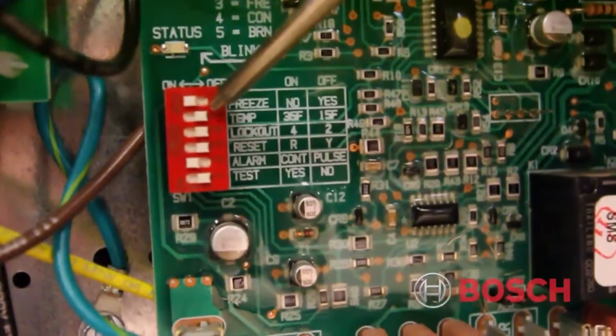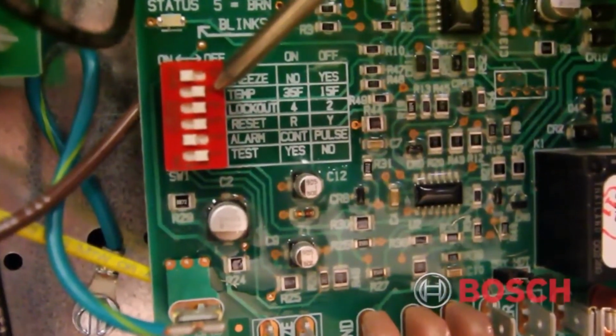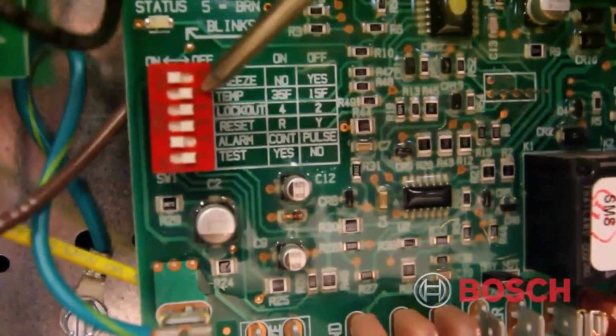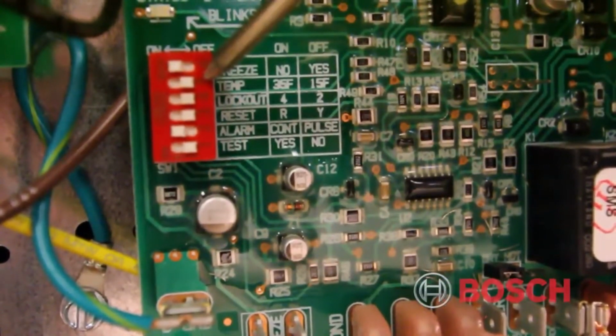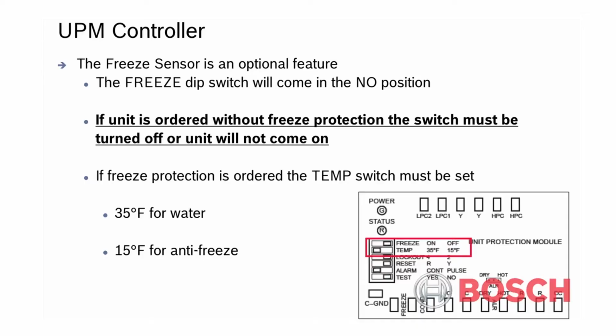The next switch has to do with the temperature cutout of that freeze protection. There are 2 settings, one at 35 degrees and one at 15 degrees. 35 degrees should be selected for systems with water in the loop. 15 degrees should be selected for closed loops with antifreeze in them.